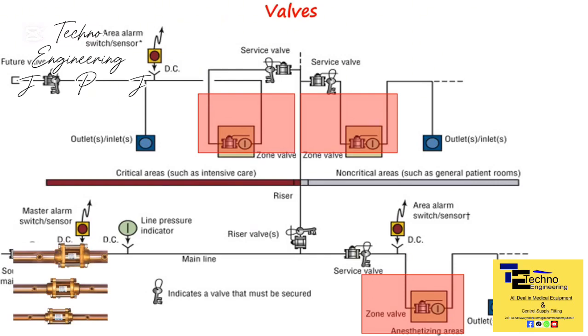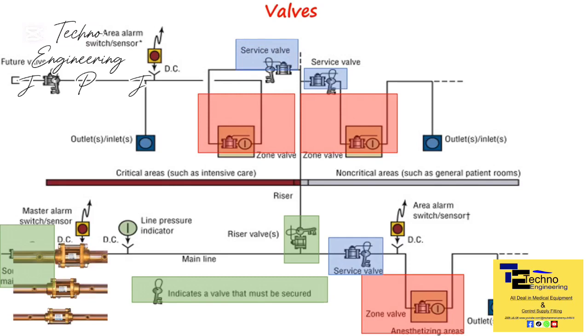Service shut-off valves, intended for authorized personnel, are secured to prevent accidental closing and strategically located for accessibility. A main shut-off valve is essential at the main supply line entry, while each riser requires one at the connection to the main line. Each branch line must also have a service shut-off valve for maintenance purposes. Check valves ensure one-way gas flow from the central source to the terminal outlet.